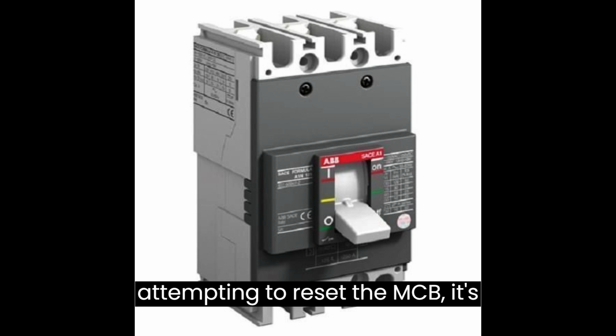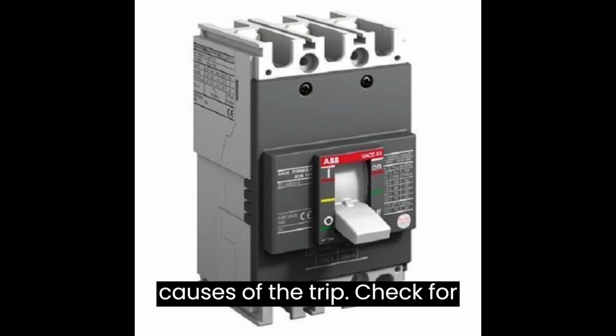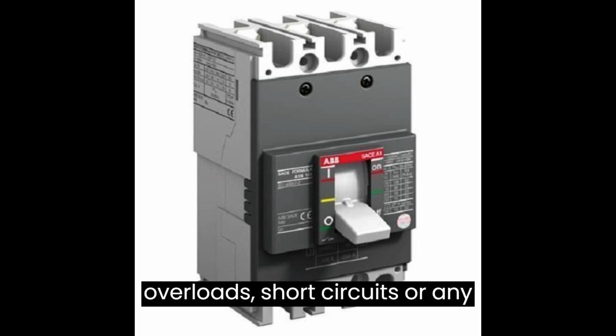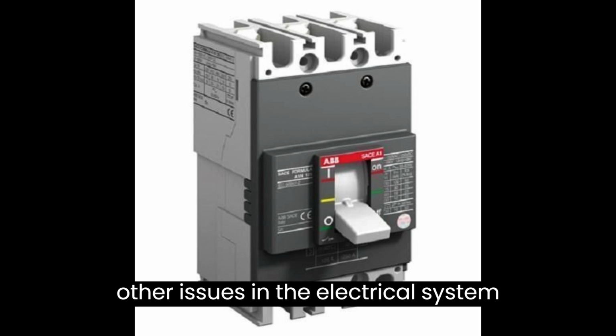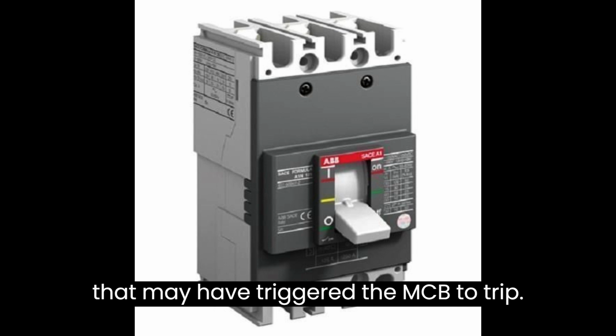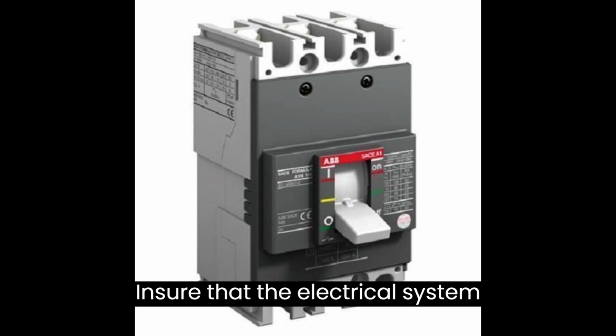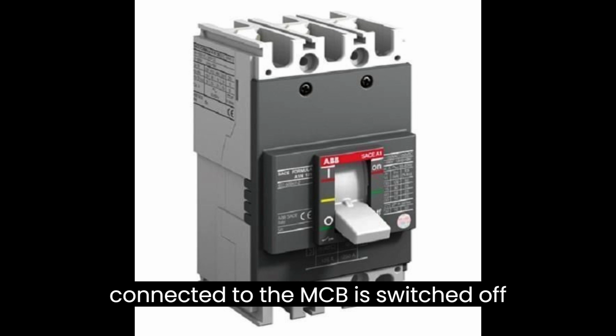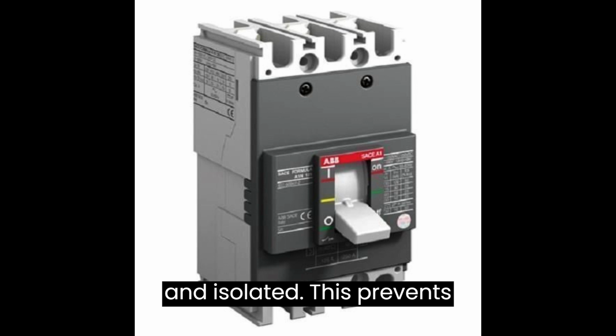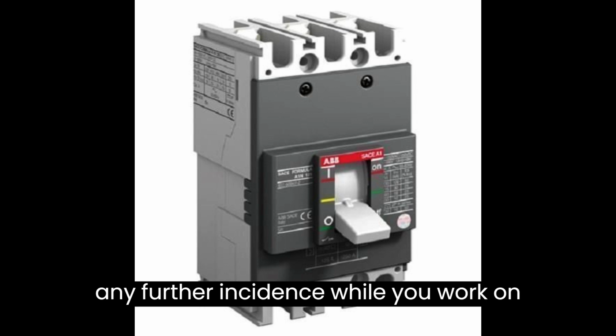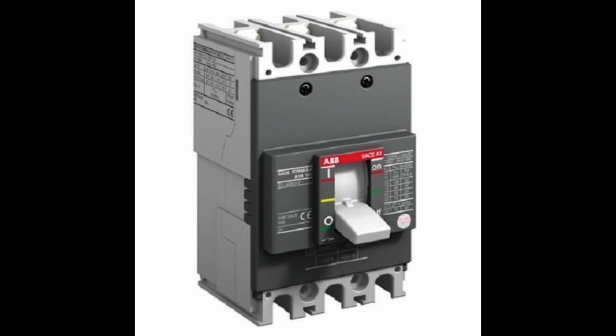Before attempting to reset the MCCB, it's crucial to identify and rectify the cause of the trip. Check for overloads, short circuits, or any other issues in the electrical system that may have triggered the MCCB to trip. Ensure that the electrical system connected to the MCCB is switched off and isolated. This prevents any further incidents while you work on resetting the MCCB.